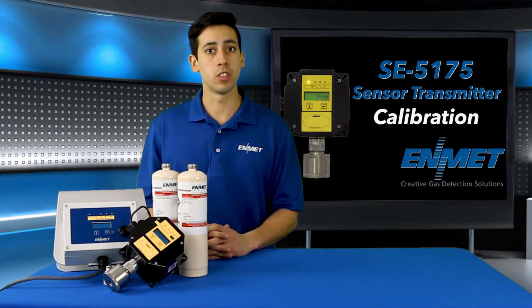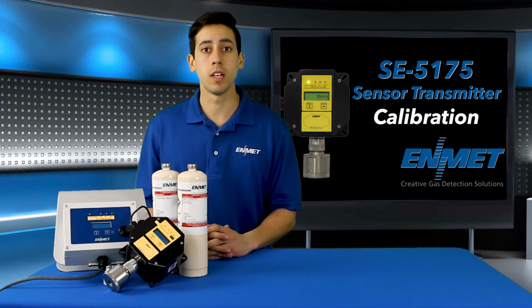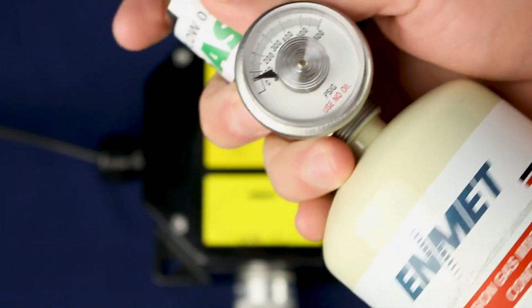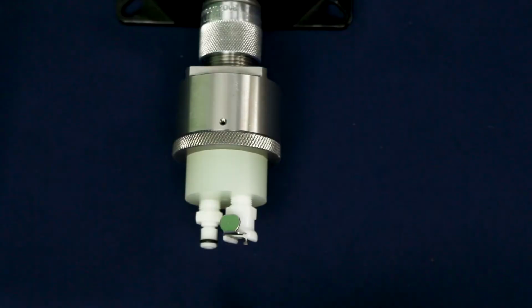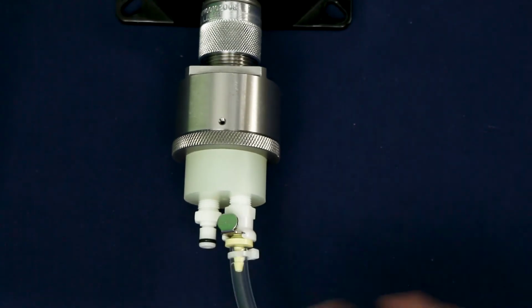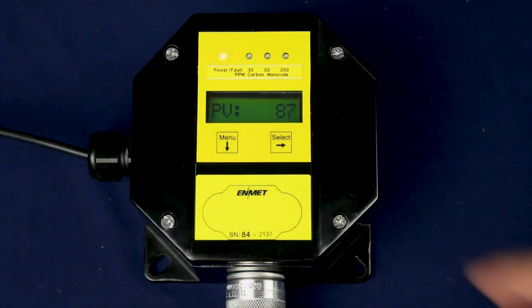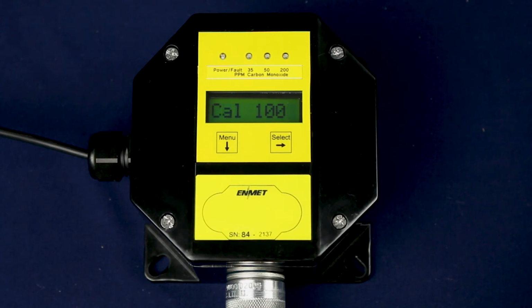The span calibration function must be performed by exposing the sensor to the calibration gas. In this case, it is carbon monoxide. If you completed the zero procedure, the span menu option should still be highlighted on the display at this point. Otherwise, use the menu key to cycle through the maintenance menu and highlight the span menu option. Connect your regulator to your calibration span gas cylinder and connect the regulator tube to the calibration adapter. Press the select button to begin the calibration procedure.